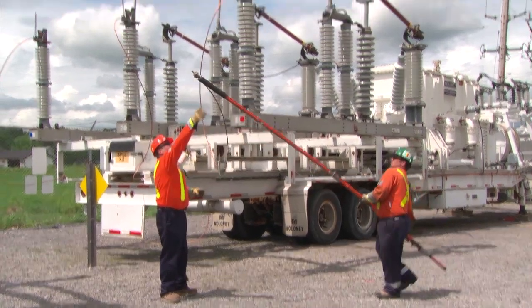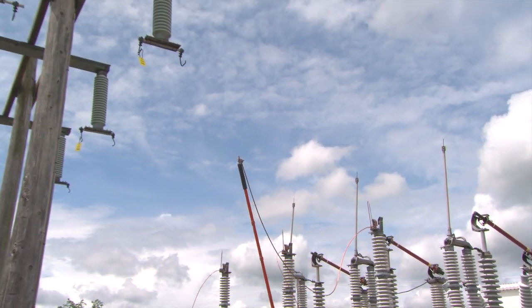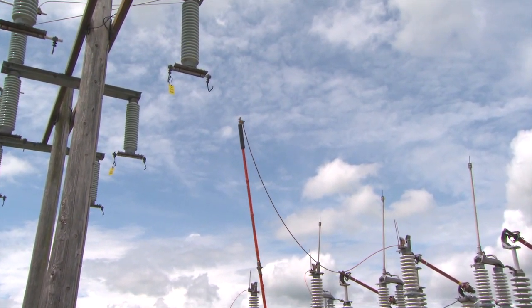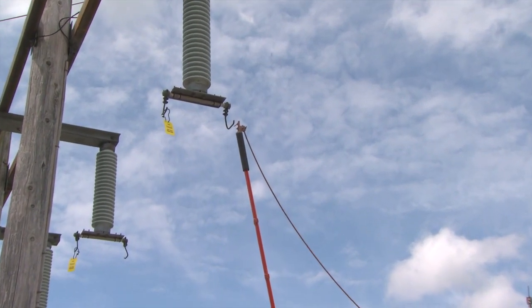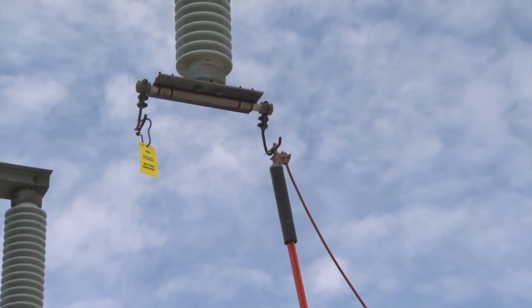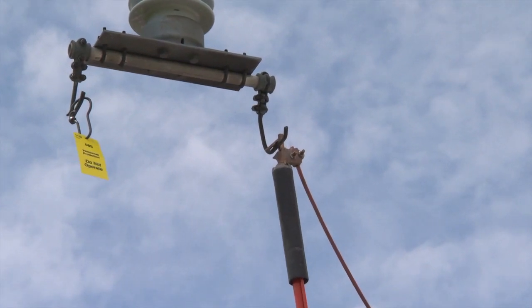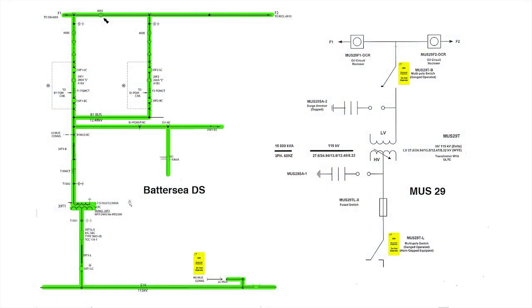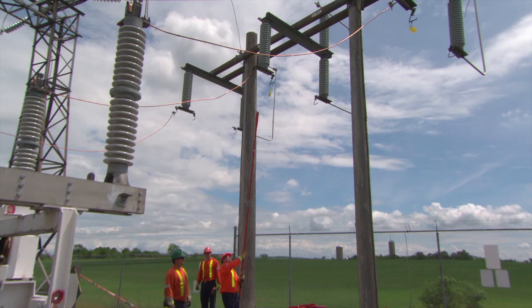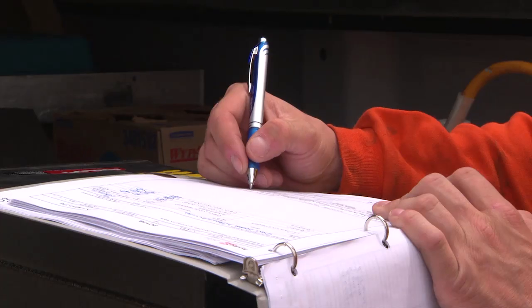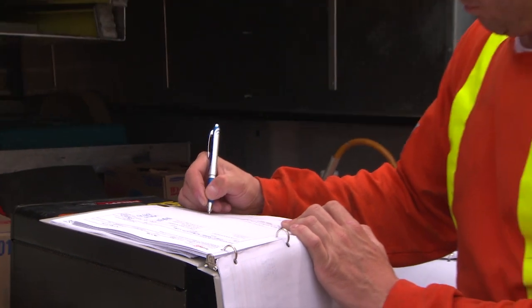Connect the high-voltage leads to the MUS structure stirrups one at a time. One hazard to be aware of is potentially having the underslung insulator fail and fall to the ground. Make sure you have your escape routes planned at all times. Once all high-voltage leads are installed, visually verify the phasing arrangement and ensure proper phase-to-phase and phase-to-ground clearances are maintained. Then surrender the self-administered work permit.